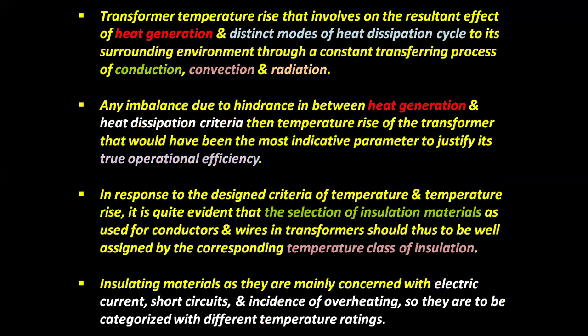Transformer temperature rise involves the resultant effect of heat generation and distinct modes of heat dissipation to its surrounding environment through a constant transferring process of conduction, convection, and radiation. With any imbalance between heat generation and heat dissipation, the temperature rise of the transformer would be the most indicative parameter to justify its true operational efficiency. In response to the design criteria of temperature and temperature rise, it is quite evident that the selection of insulation materials used for conductors and wires in transformers should be well assigned by the corresponding temperature class of insulation.